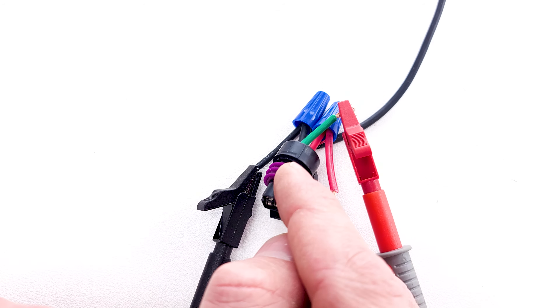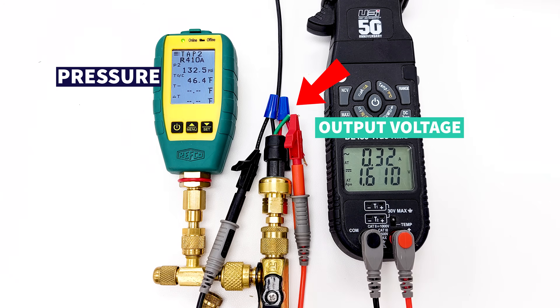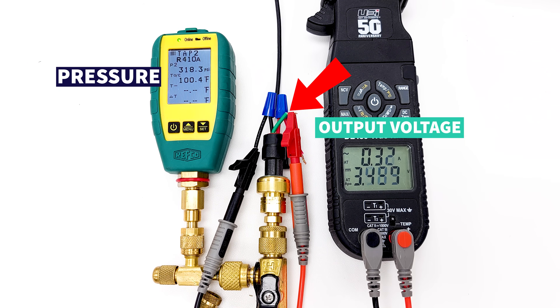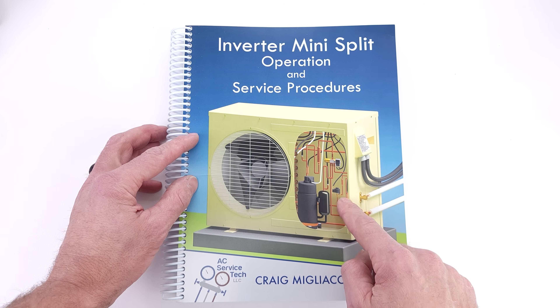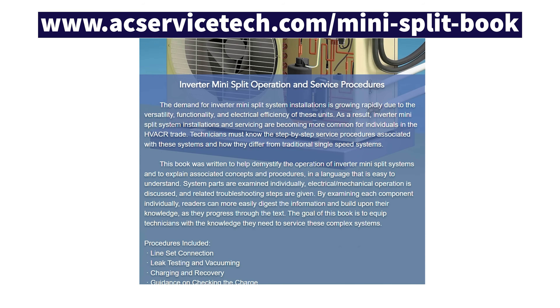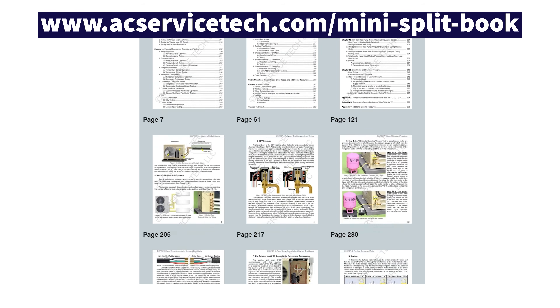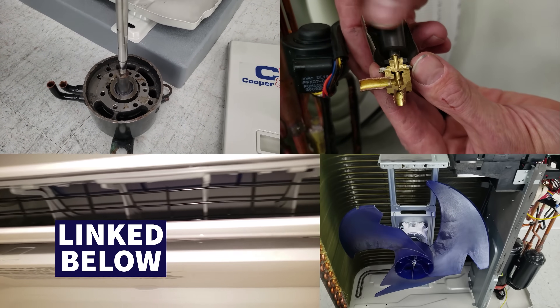As far as us technicians are concerned, we're measuring the voltage applied to the sensor and the output voltage to determine the pressure at the port. You'll also want to measure the actual pressure at the location where the pressure transducer is installed and compare that to the output voltage on your signal wire. If you want to learn more about mini split systems and the electrical components inside, check out our inverter mini split operation and service procedures book at acservicetech.com in the mini split tab. Also check out some of the mini split install and service videos linked in the description below.